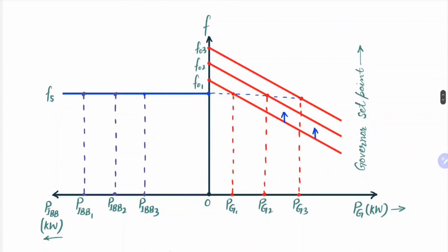As soon as the alternator is connected to the infinite bus bar — once it is synchronized — it will start floating. Floating means neither it will supply active power nor consume active power. However, keep in mind that it will supply a very small active power which can be ignored. Now we are going to increase the mechanical input to the alternator by increasing the governor set point.